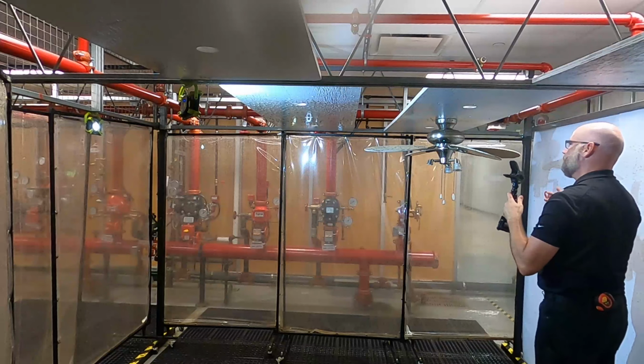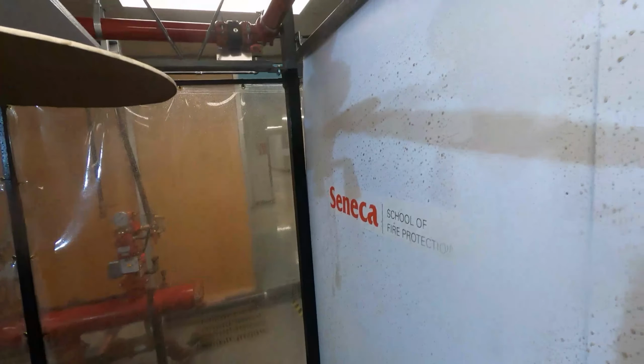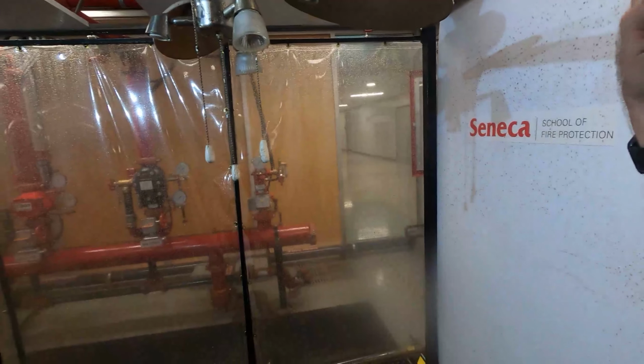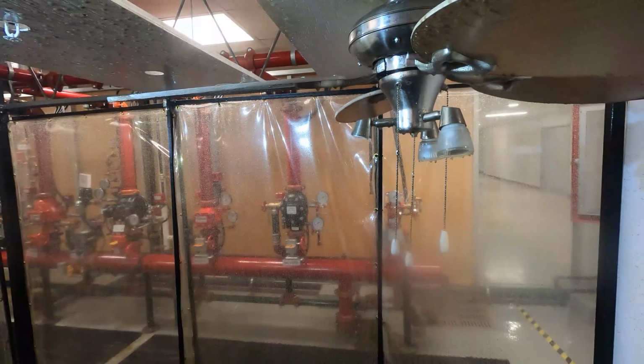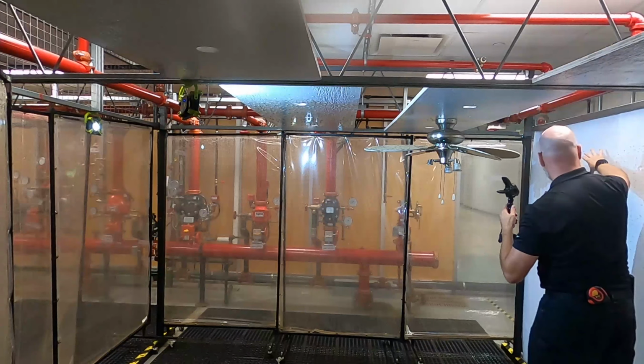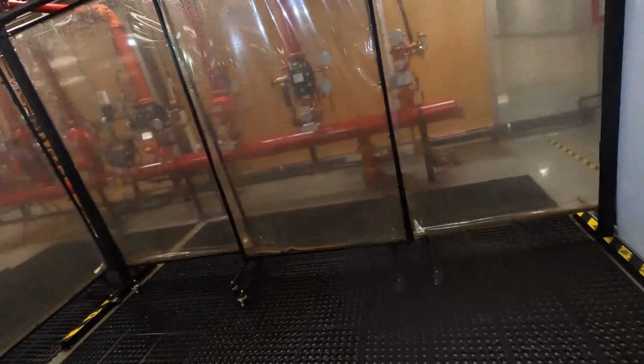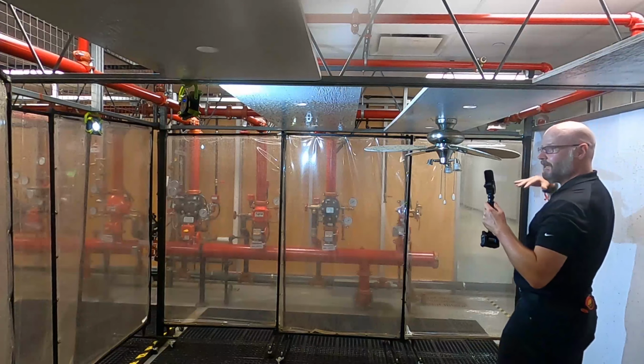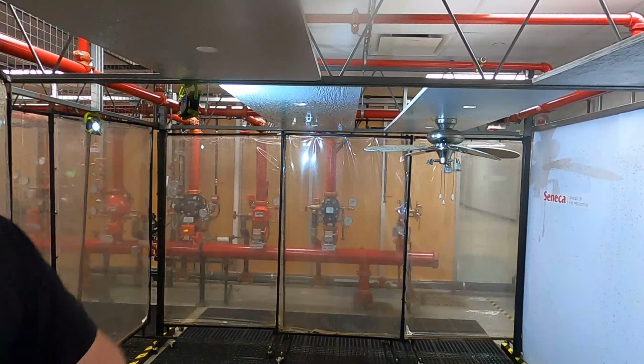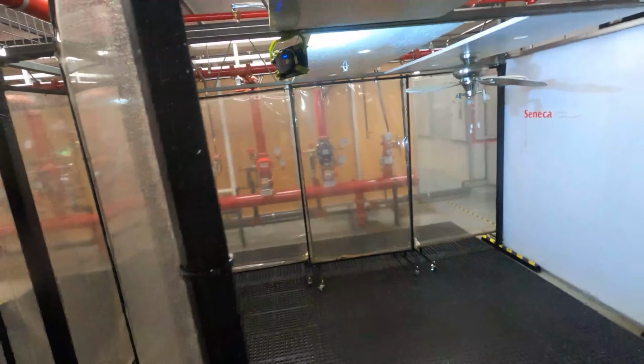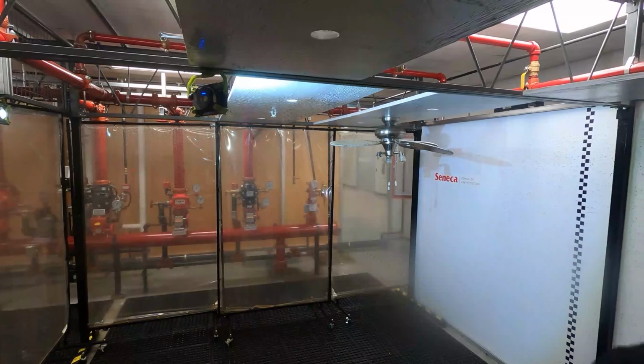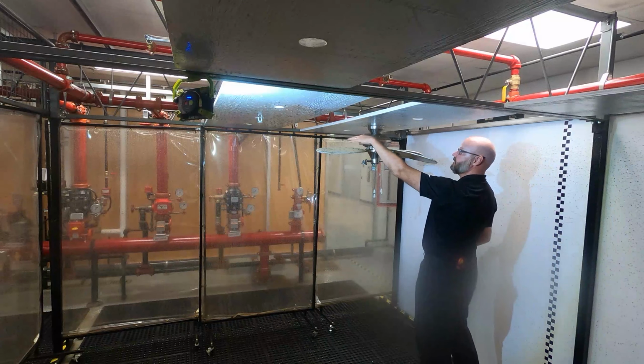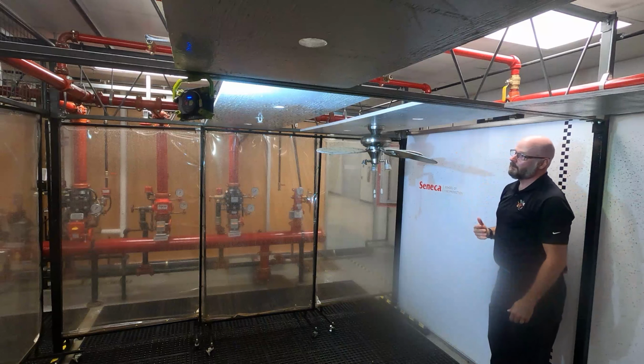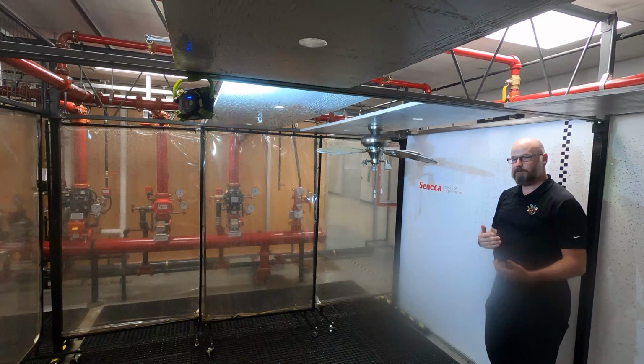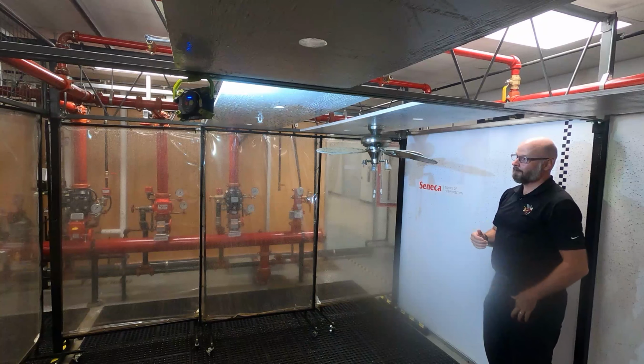So the obstruction, the distance, we'll look at that to see what the impact would have been. However, you can see that in that close proximity, the body of the fan certainly created a problem for us, and then its impact on the white wall. We have some water discharge that's higher, likely came scooting right across the top of the obstruction. Again, that's why the shape of these is really important to understand. The shape of your obstruction in that configuration, I would say most of the water went directly across, and we were able to minimize the actual obstruction just based on the features of the ceiling fan.